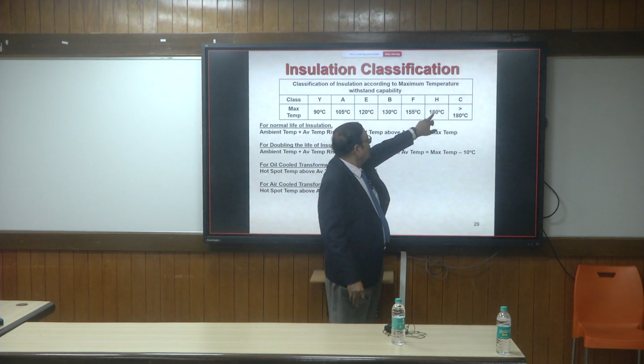Most of these varnishes will not be air drying. You have to cure them, put them at a certain temperature for certain hours. Within that, you may find that some of the coils have magnetic components that are not giving their desired performance. Why? It's not because of insulation, it's because of the curing temperature of the core.